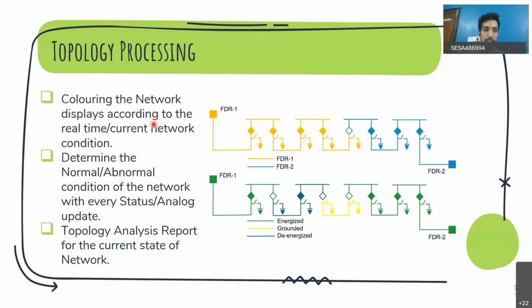Coloring of the network displays is done according to real-time or current network conditions. For example, if you have a ring between feeder 1 and feeder 2 with 4 RMUs, feeder 1 feeds through RMU 1 and 2 and is kept open at this RMU, while feeder 2 feeds the other direction. The coloring is done so that at first glance the operator understands feeder 1 covers up to this point and feeder 2 up to that point. A legend shows, say, orange for feeder 1 and blue for feeder 2.